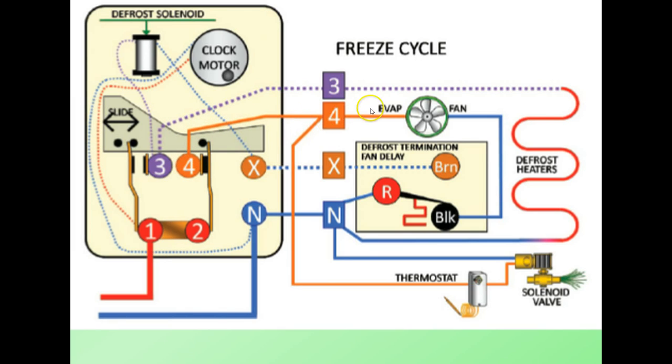We're on the neutral side of the evap fan, so we do have 115 volts coming to the fan. Let's follow this neutral back, see if we have a complete circuit through the defrost termination fan delay back to neutral. We have a complete circuit. The fan is operating.